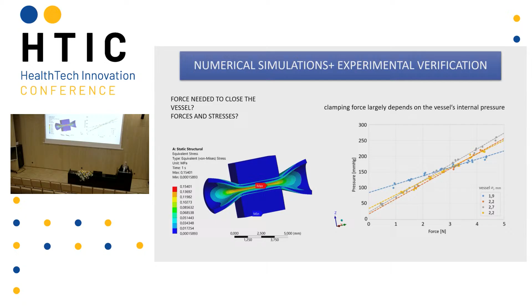And the main findings: we defined these forces, and the main clamping force largely depends on the vessel internal pressure and also diameter. We also performed histopathological evaluation just to show that if we use excessive clamping forces, which are higher than the defined occlusion forces, we are getting major tissue damage. Here you can see native tissue, not stressed, and also tissue after the pressure sampling with the application of the excessive clamping forces.